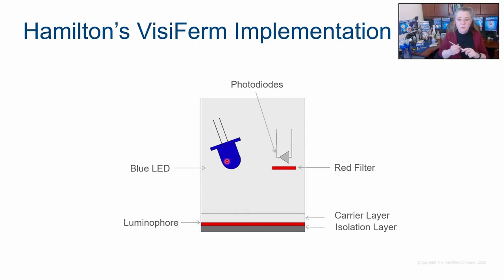So instead of doing that, Hamilton goes with a single light and we use a filter. How do manufacturers with two lights do it? Either you have to do a lot of extra calibration and/or they limit how long the probe is useful for. They know that after so many operating hours, the difference between the two lights is so significant that they say the probe is no longer valid and must be replaced, because they can't control the difference.